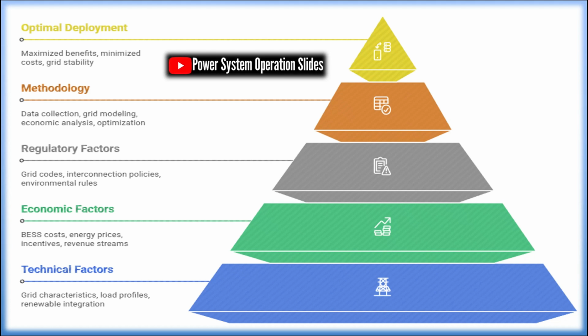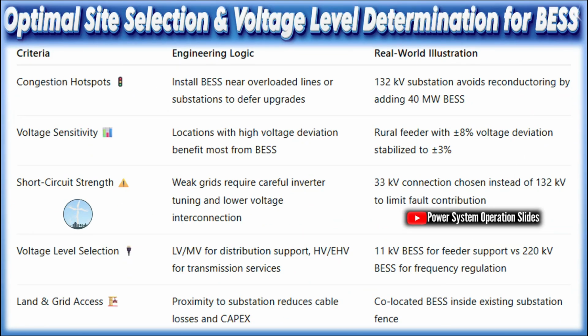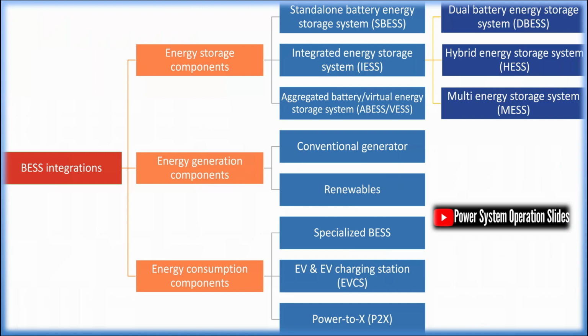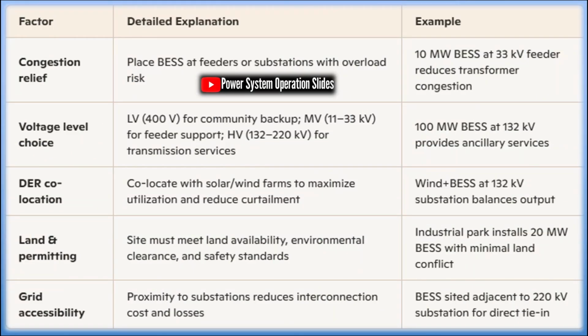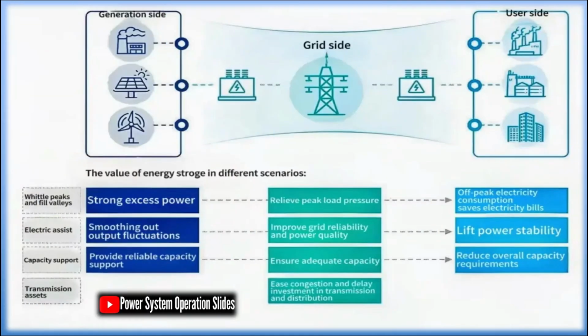BESS addresses these challenges through multiple technical mechanisms. Time-shifting energy, achieved through peak shaving and valley filling, allows energy to be stored during periods of low demand and discharged during peak demand periods, effectively flattening the load curve and reducing the need for peaking generation capacity. Synthetic inertia and fast frequency response, FFR, capabilities enable BESS to respond to frequency disturbances within milliseconds, providing the grid with the rapid response capabilities needed to maintain frequency stability in low inertia environments.